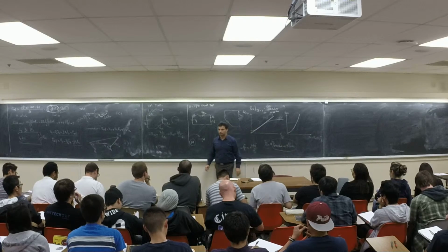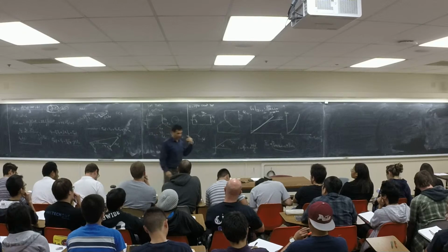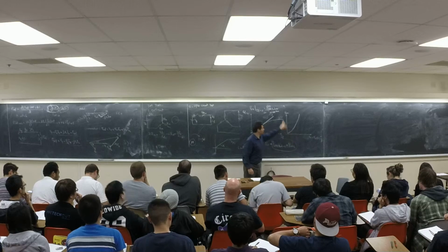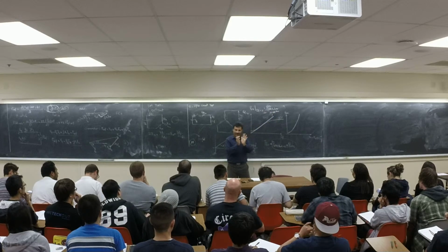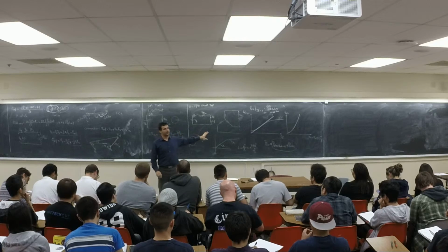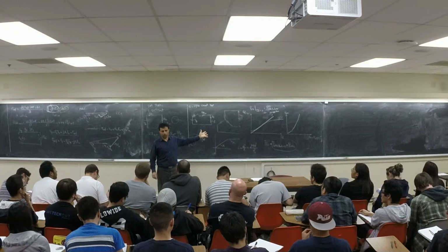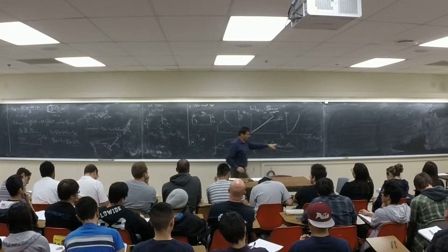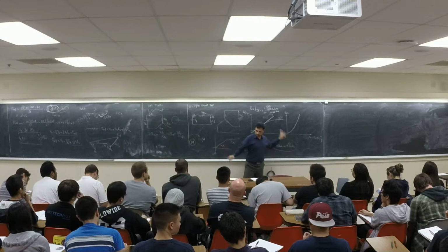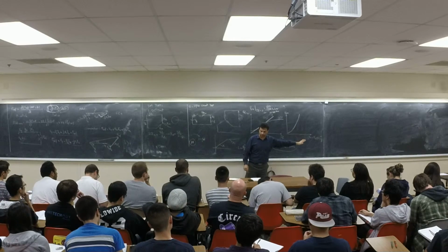If you want to separate these two to see how much is this one and how much is this one, what should I do? I'm going to open the excitation system, right? If I open the excitation system, this one is gone, so I'm measuring only the other. You can separate the mechanical loss and the core loss. And by the way, we call this one constant power loss, because when you are at the rated voltage, P core is hysteresis and eddy current. The machine is rotating at synchronous speed. The voltage is fixed. The frequency is fixed, right?